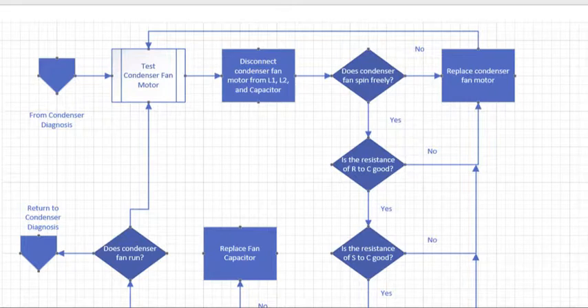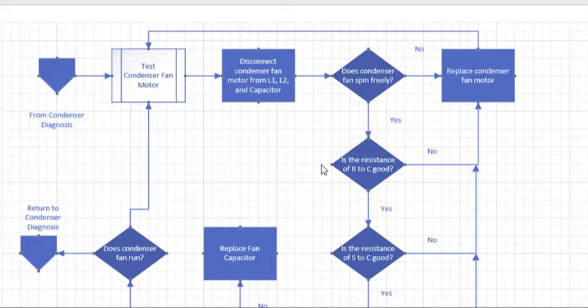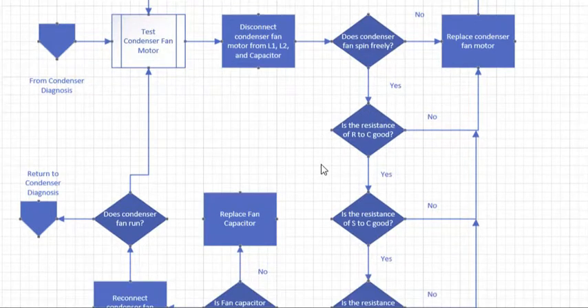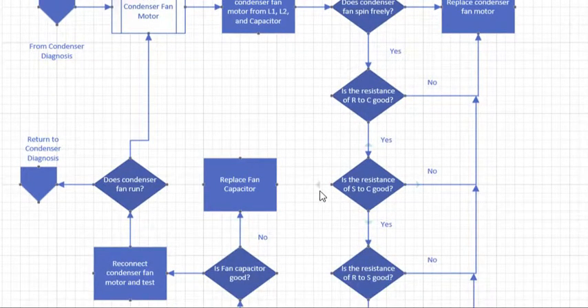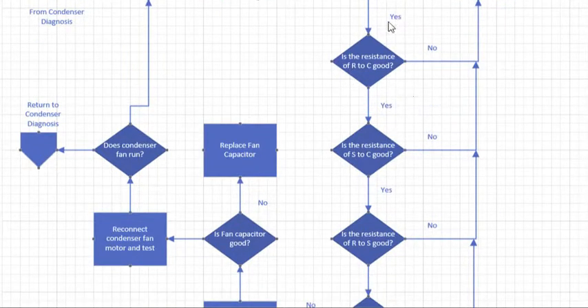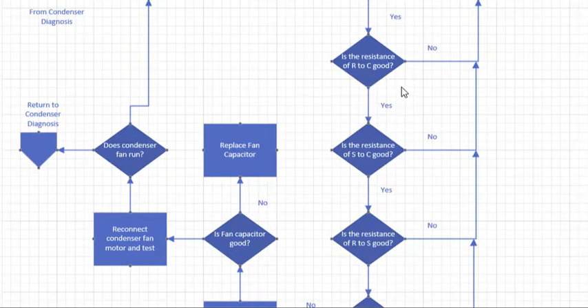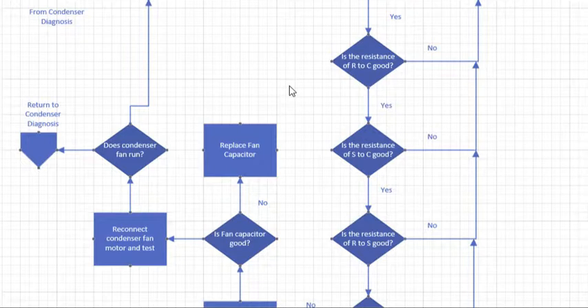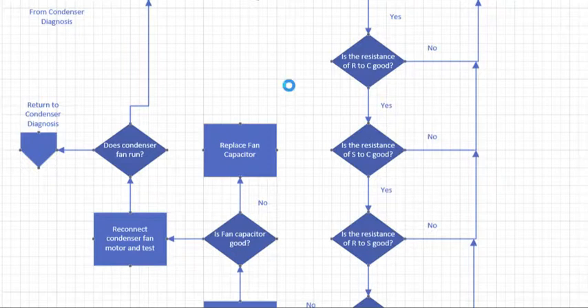If the condenser fan motor does spin freely, check for resistances between R and C, that's run and common, S and C, start and common, and R to S. What you're looking for in these is some numbers. You do not want a zero and you do not want your meter to show infinite or OL. Zero and OL are bad readings for resistances across windings. A zero means that winding is shorted. OL means the winding is open.